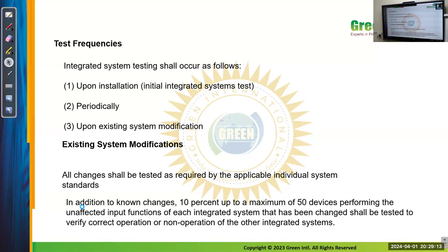And upon existing system modification. We studied this in NFPA 13, if I believe correctly: if one sprinkler is replaced, we don't have to perform this, right? But the test shall be performed when, say, 20 sprinklers are replaced in the system. That comes under the modification of existing systems. If such modifications are done, we have to do the integrated testing again, not only the hydro testing.